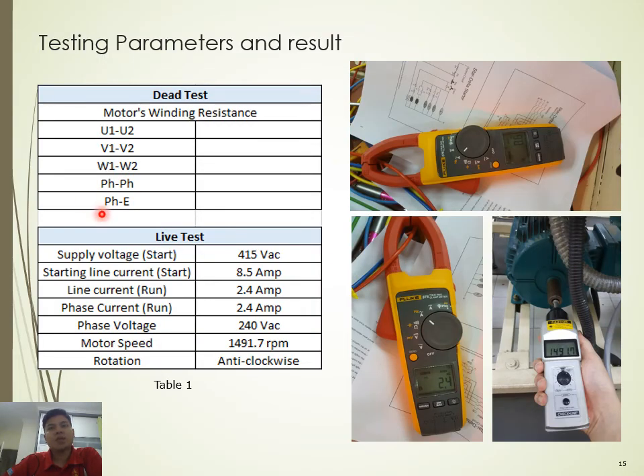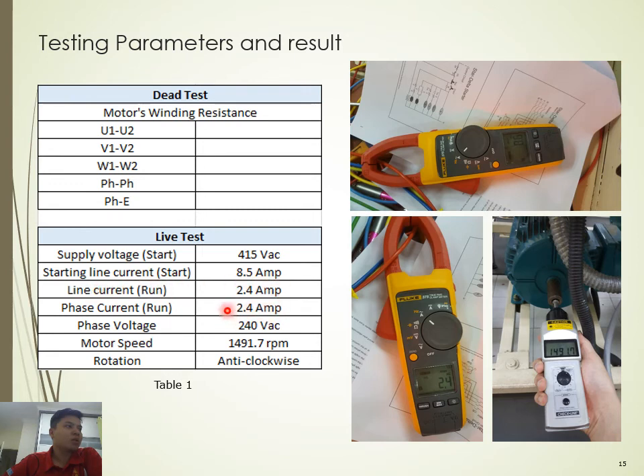The testing parameters and results: the supply voltage is 415V AC. The starting line current when powering up the motor is about 8.5 amperes. The line current during running is 2.4 amperes and the phase current is also 2.4 amperes — these are equal because the motor is running in star connection at that point. The phase voltage is 240V and the motor speed is approximately 1491.7 RPM; the rotation is anti-clockwise.